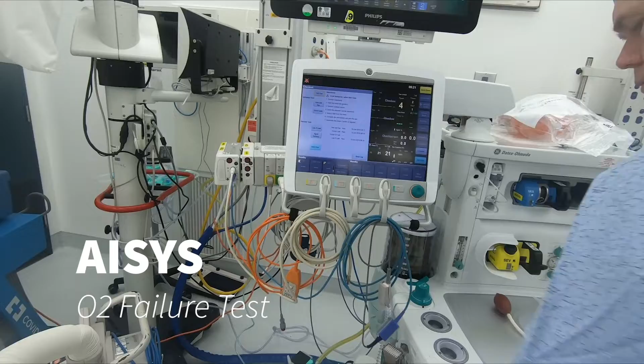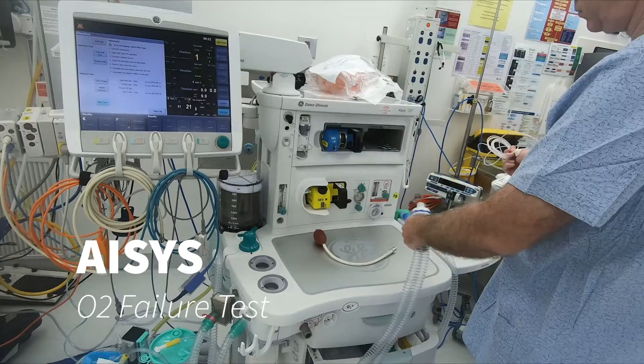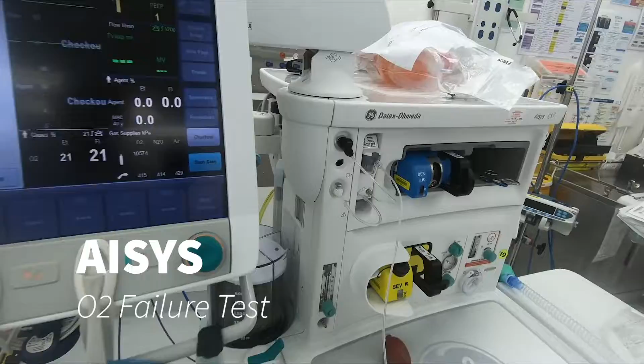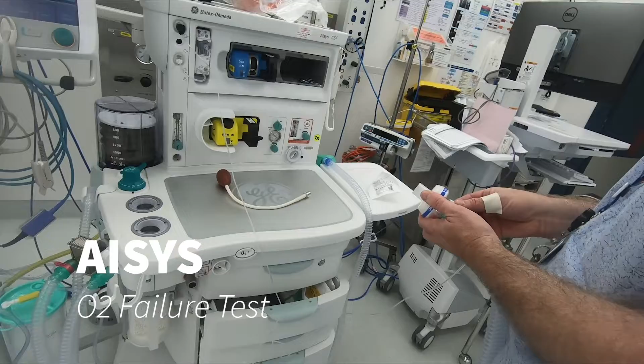Okay, what we're going to attempt now is do 50-50 with oxygen and nitrous, and we're going to do an oxygen fail. So we connect the filter to the circuit and run the sample line. So you can see here, that's the sample line unit, and that goes into a filter. Perfect.